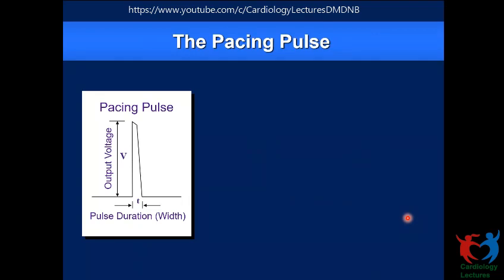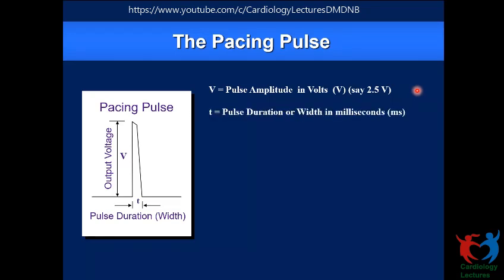So here we would like to look at one pacing pulse in a little more detail to understand the energy outgo. Let's assume that we are delivering a pulse at an output of 2.5 volts, and we are delivering it for a duration of 0.5 millisecond, which is usually the nominal pulse duration in most pacemakers, 0.4 or 0.5 milliseconds. And then we measure the impedance. Impedance is not in our control, so we measure the impedance of this pacing circuit. It happens to be 500 ohms.